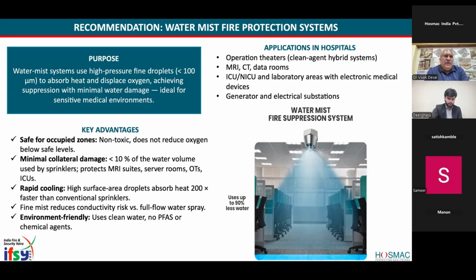So it can be pretty useful, especially in sensitive areas. Plus, the other advantage is you don't need a large water tank capacity to fight fire. If you are able to do this using a mist kind of system, which rapidly cools, it reduces the collateral damage and is environmentally friendly because it uses less water. So you can use this in some operating rooms and ICUs where otherwise we don't use firefighting systems. This is a new kind of system which one can look at.